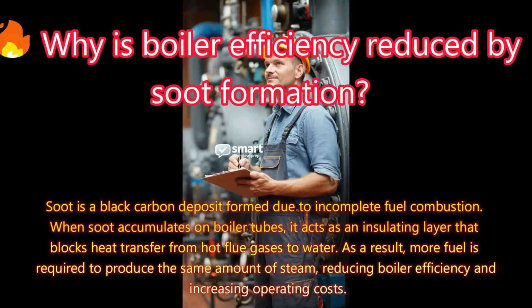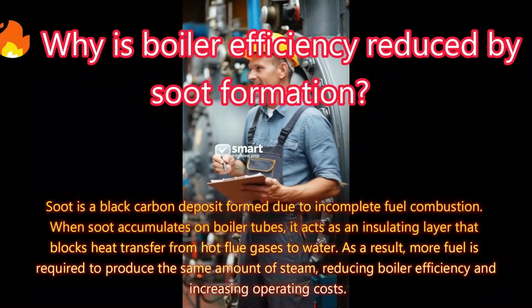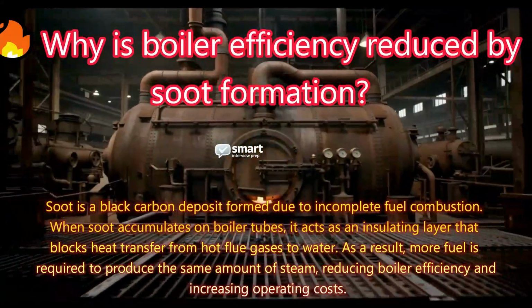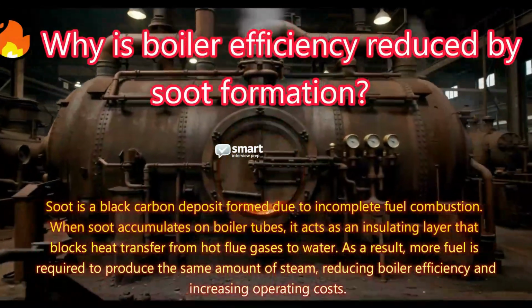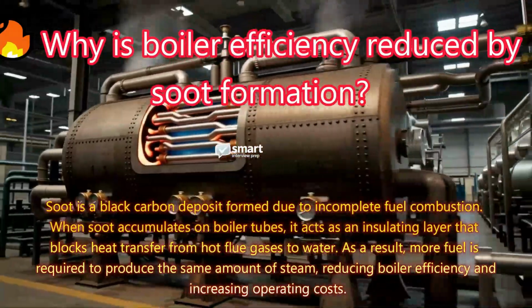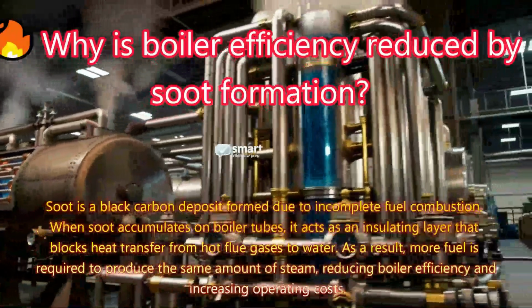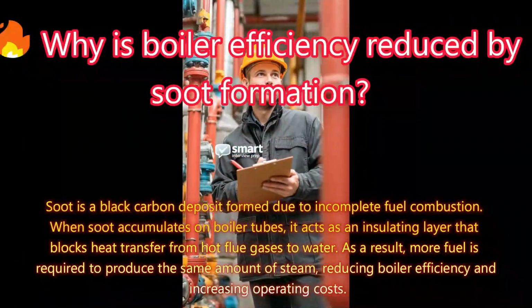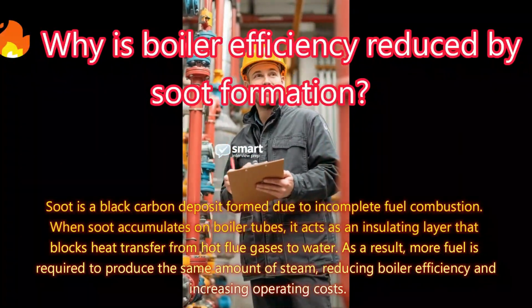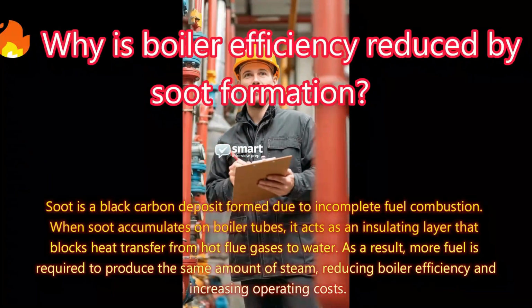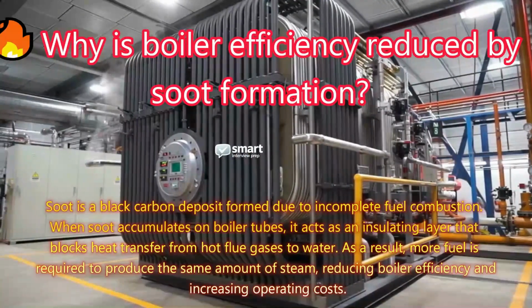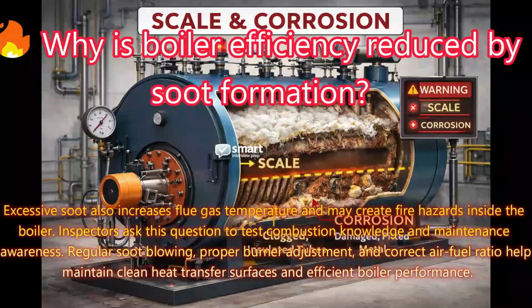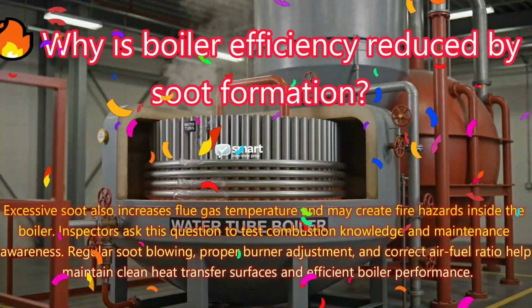Answer. Soot is a black carbon deposit formed due to incomplete fuel combustion. When soot accumulates on boiler tubes, it acts as an insulating layer that blocks heat transfer from hot flue gases to water. As a result, more fuel is required to produce the same amount of steam, reducing boiler efficiency and increasing operating costs. Excessive soot also increases flue gas temperature and may create fire hazards inside the boiler.